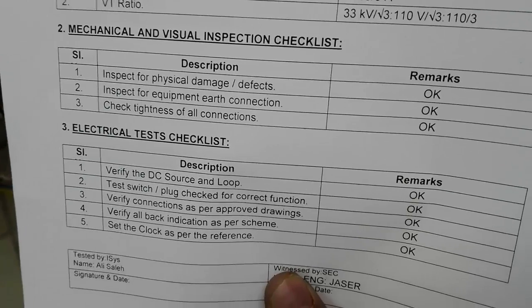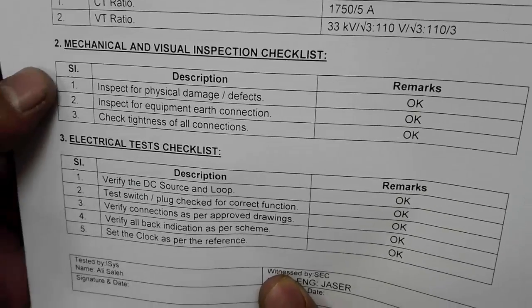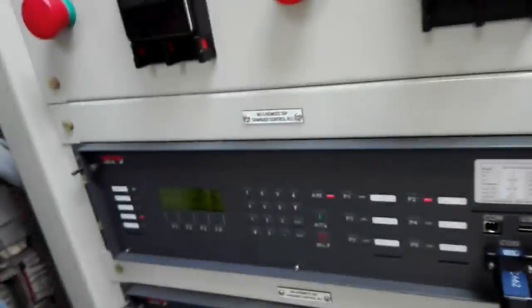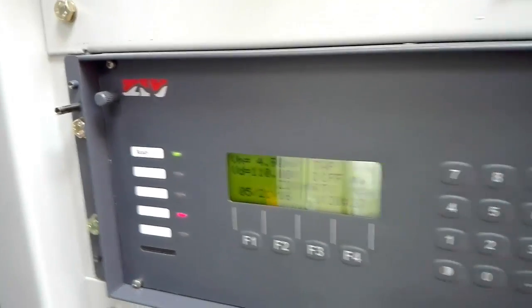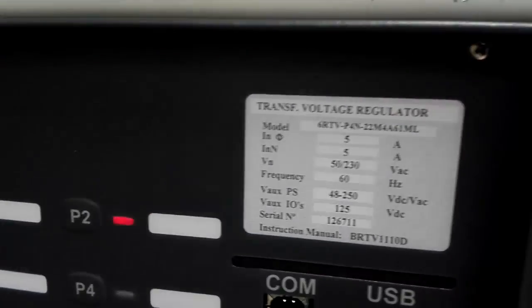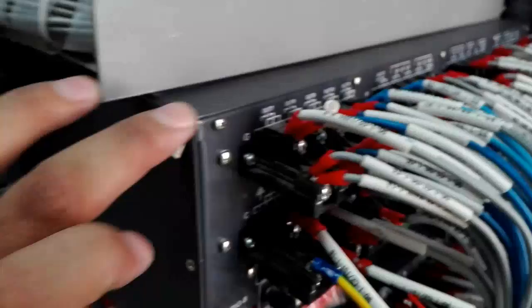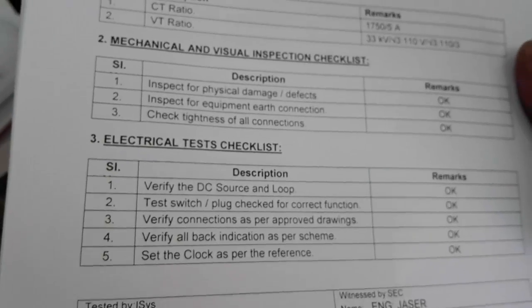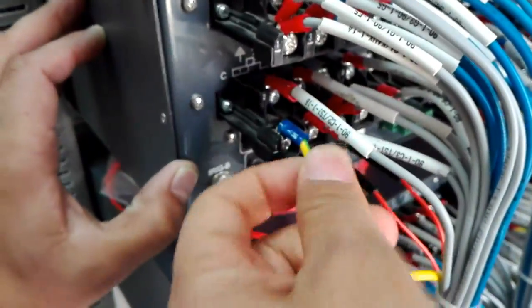Before any test, it is advised to do the mechanical and visual inspection checklist. Inspect for physical damage or defects. So, see here, any defect we see here? No, if no, we will make it okay. From the back side, can you go to the back side, please? Here, see this also. Any damage? No damage. Then inspect for equipment earth connection. Now, where is earth? Yeah, this one. So our connections are also okay.